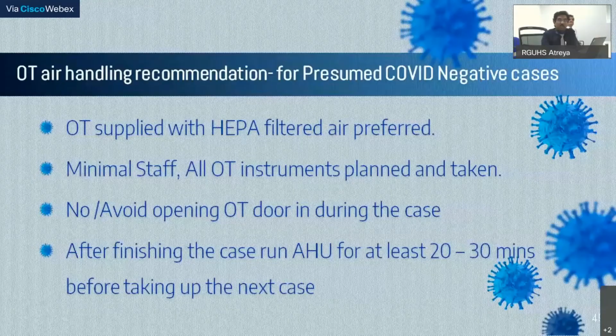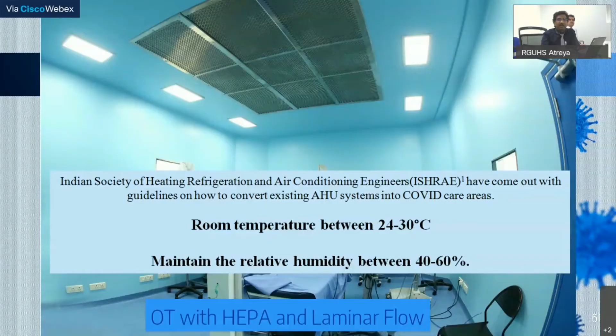The Indian Society of Heating, Refrigeration and Air Conditioning Engineers, ISHRAE, has come out with guidelines. The room temperature should be set between 24 to 30 degrees, and we should maintain relative humidity between 40 to 60 percent. So it's better to use an OT with HEPA and laminar flow.